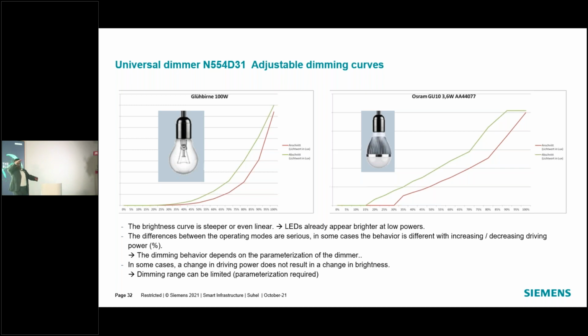So what we do here is define a smooth dimming curve for all these 5 lamps. I start from 0 to 100% dimming, and I tell my controller to define a smooth dimming curve for these 5 lights. The controller will determine that in order to have no flickering, you need to start with 20% of the power and then go to 100%. When you dim down, you also have to stop at 20%, don't go below that, otherwise flickering will happen. This is what the controller does, and by doing this we guarantee there will be no flickering of LEDs.